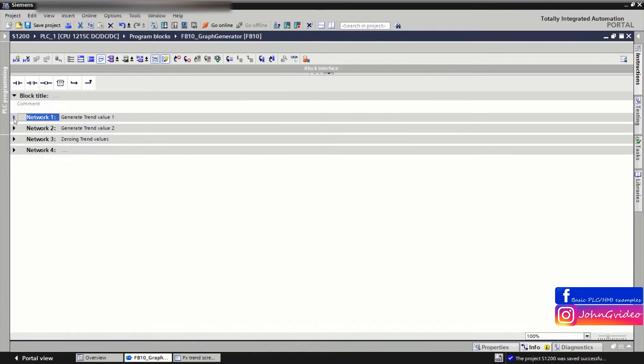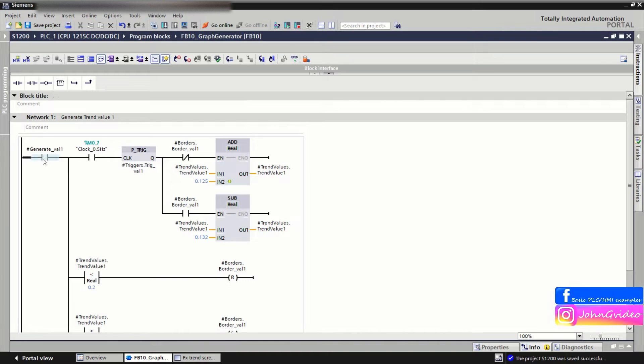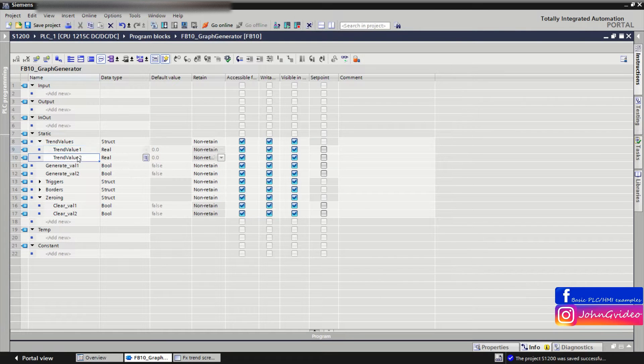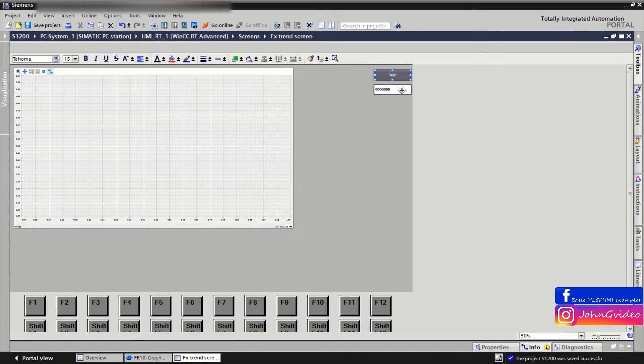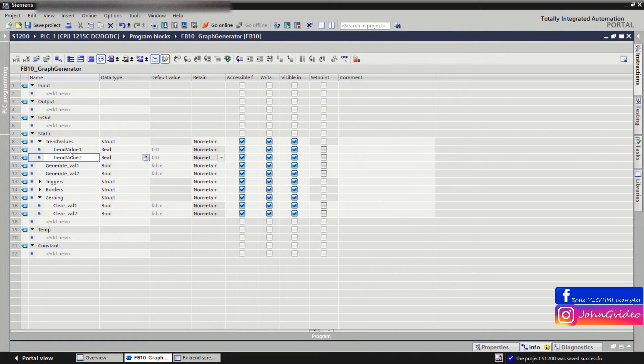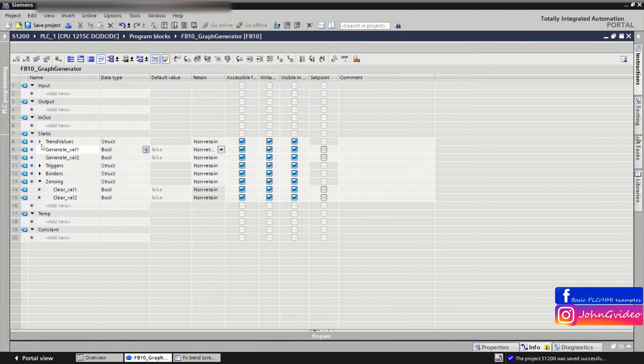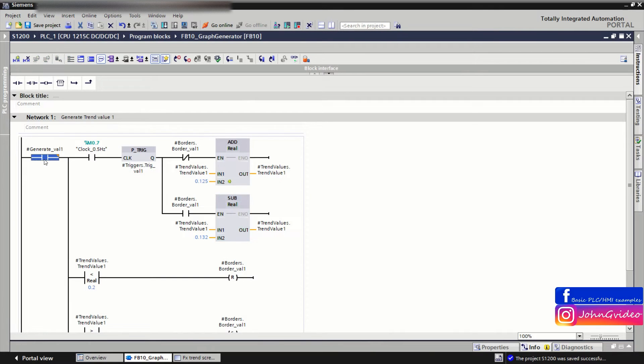Looking at our code: to start generating values we use this static tag of function block FB10. We create static tags — one is a structure called 'Trend Values' which contains trend value 1 and trend value 2. These two values are used for showing the actual trend variable value and also for the trend data. We also have generate value 1 and generate value 2 for starting the value generation.